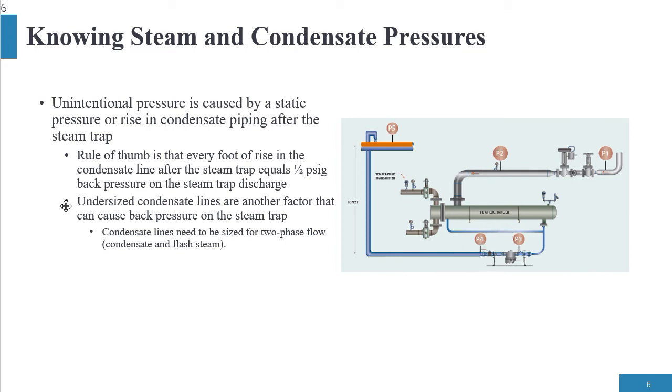The other factor is that undersized condensate lines, which I already mentioned, is a big factor today in steam and condensate systems. Therefore, 95% of the time we're going to have back pressure onto the system.